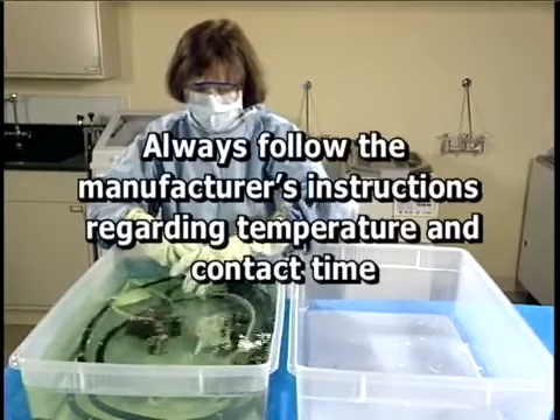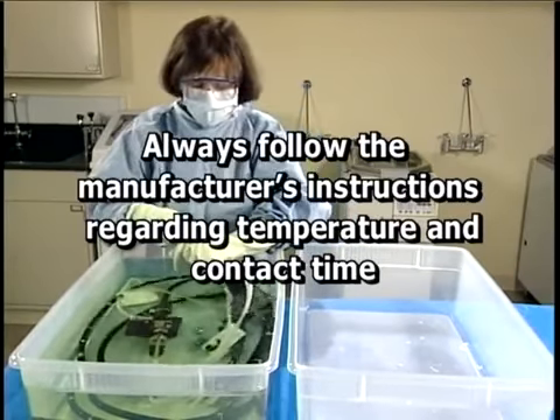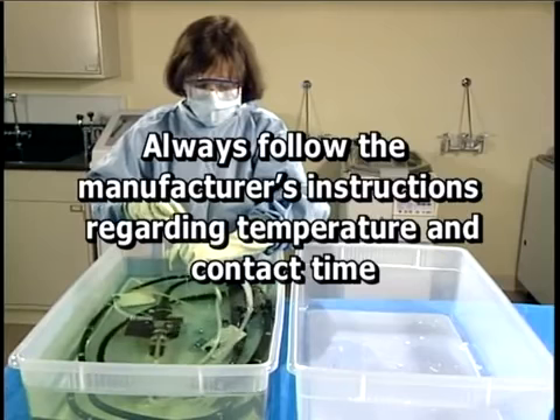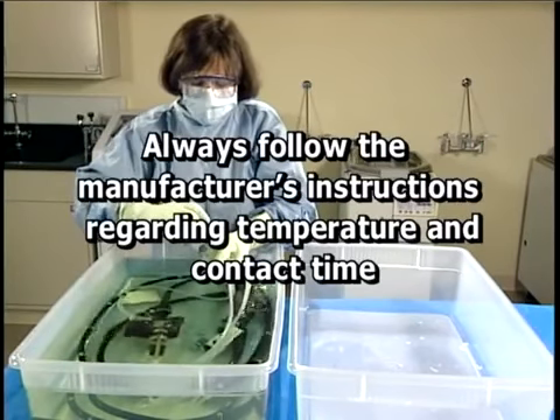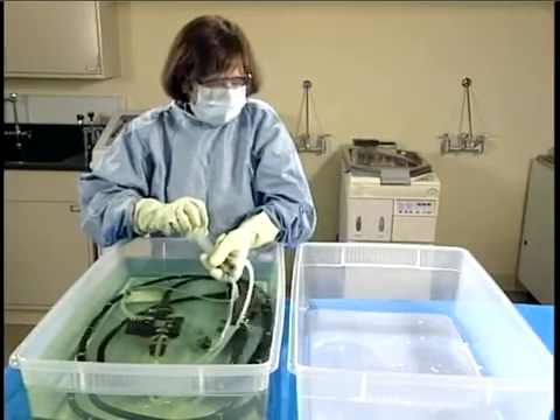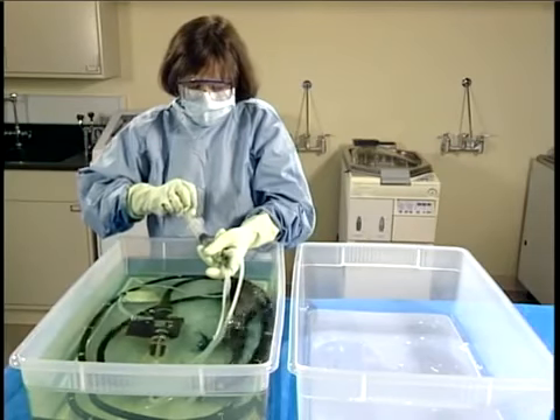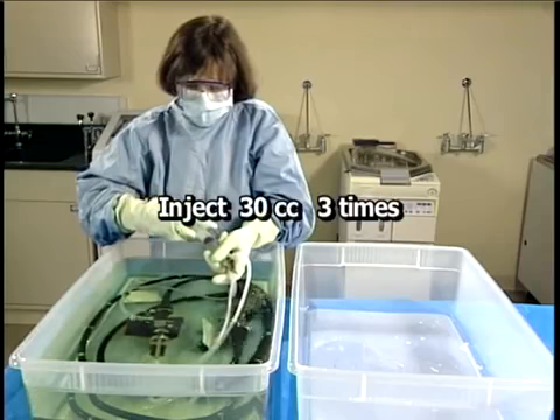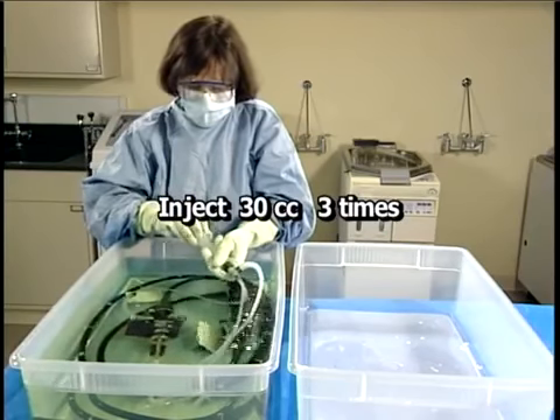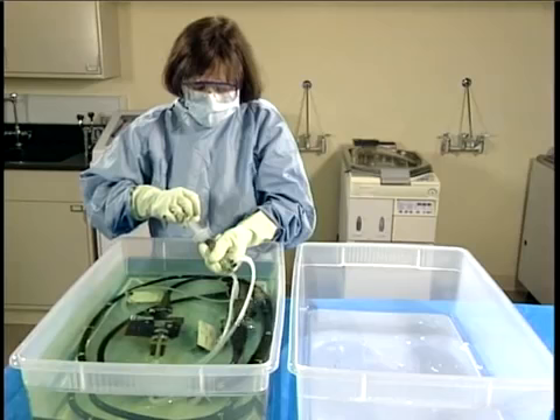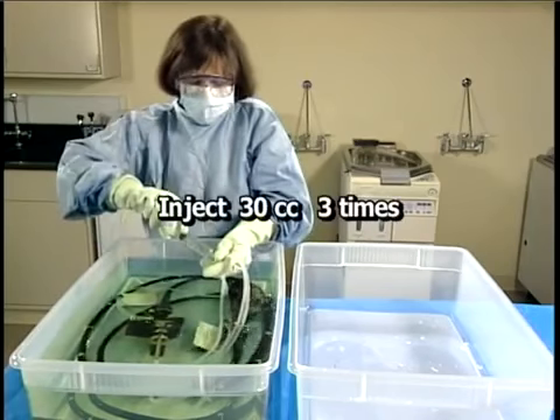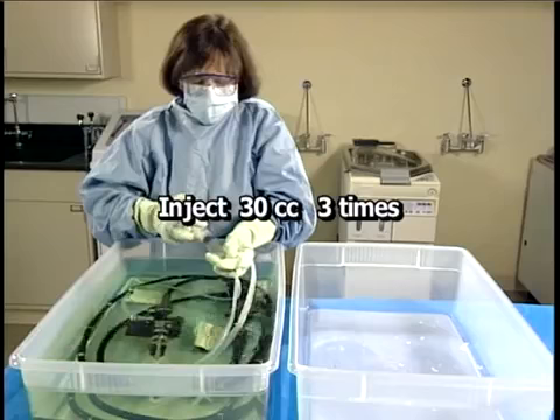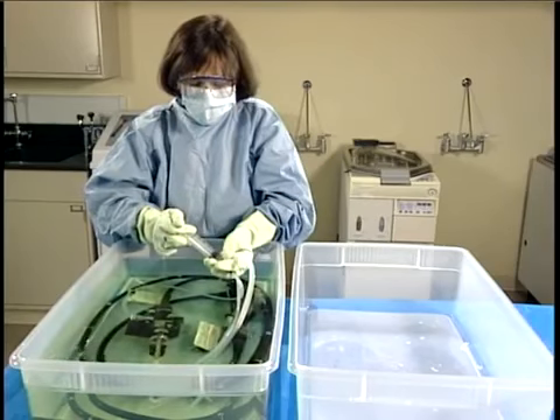The solution must be tested for efficacy and prepared according to the manufacturer's recommendations regarding temperature and contact time. With the intake filter immersed in disinfectant solution, use the syringe to inject 90 cc's of disinfectant into the air-water channels. Repeat this procedure with the syringe attached to the suction channel port. The endoscope's air, water, and suction channels are now completely filled with disinfectant solution.